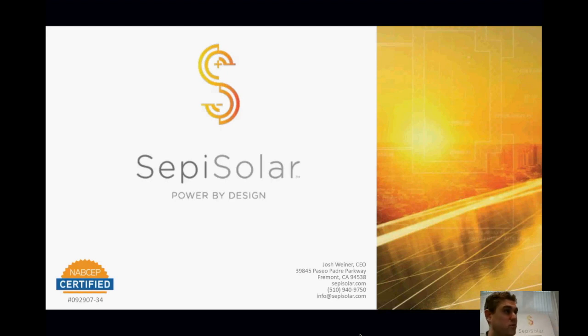Let's say you're trying to follow the 120% rule with solar and storage, and there's more you want to add that you don't have capacity for. Some workarounds are to decrease the size of the main service breaker. A lot of us are familiar with that method. It's often accompanied by load calculations, often stamped or sealed by a licensed electrical engineer. And by the way, Article 220 of the code...